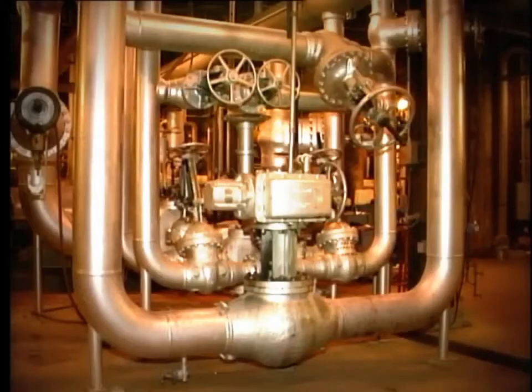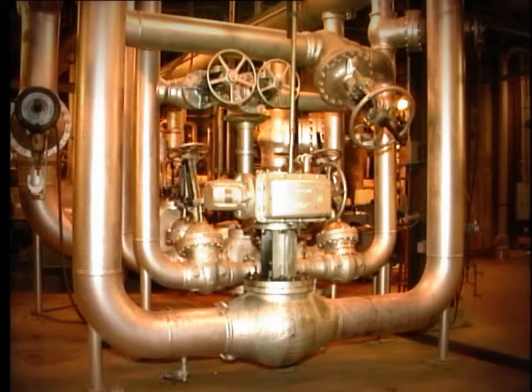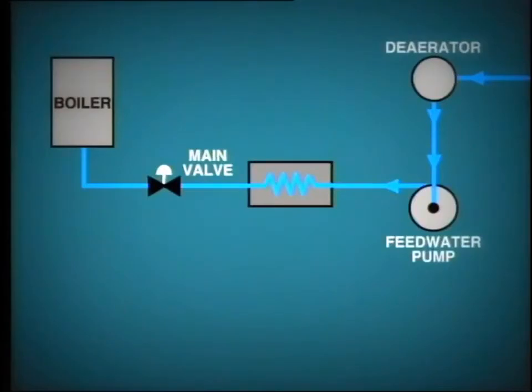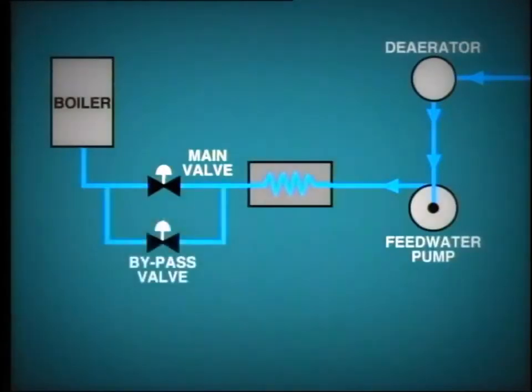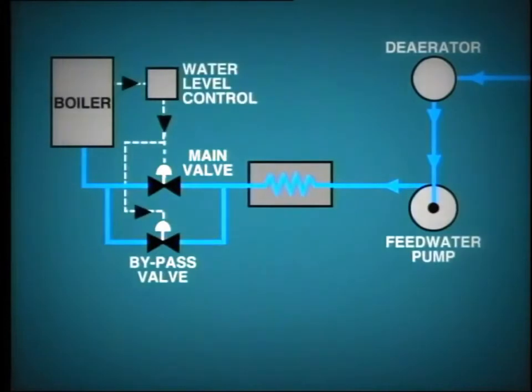One of the most common forms of boiler feedwater control is affected through a modulating feedwater control valve. This valve is usually operated according to signals from the boiler control system. In order to provide finer control at low loads, a small bypass is usually fitted complete with a control valve. The two valves operate together in response to signals from the boiler water level control system.